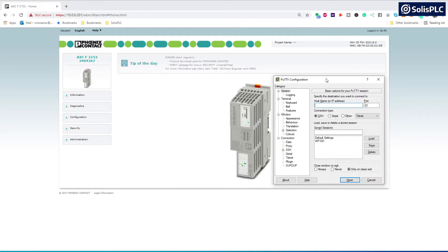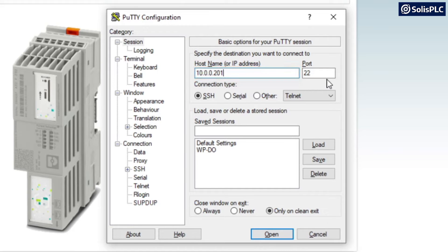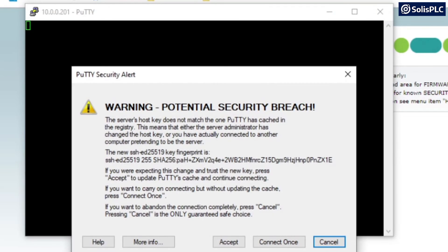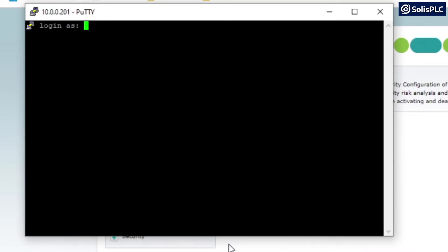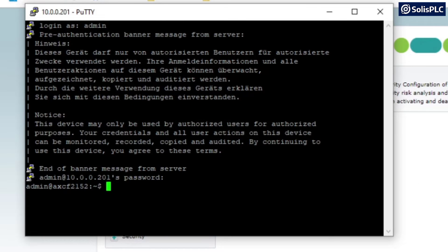To connect to our PLCnext, we're going to use PuTTY, a very common SSH application that allows you to connect to many Linux-based devices. I'll need a host name, which is the IP address we've just created — 10.0.0.201 — and we'll keep this on port 22. We'll open the connection, accept the warning, and we'll be prompted for the login information, which is the same as we entered on our PLC.